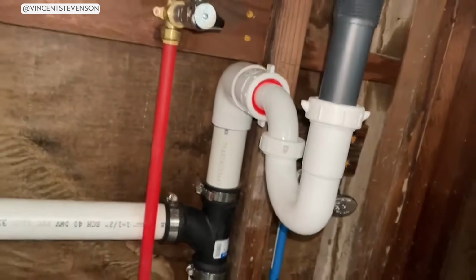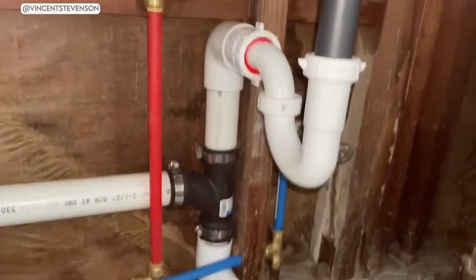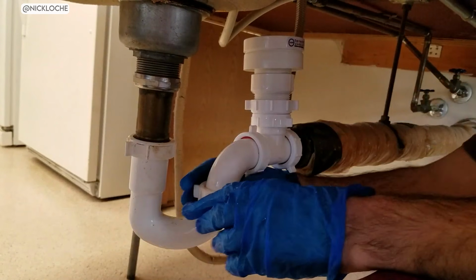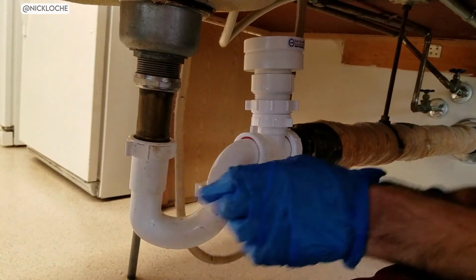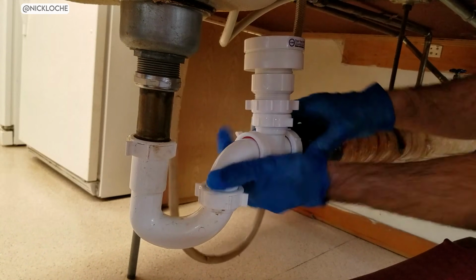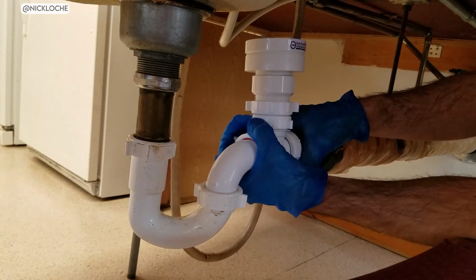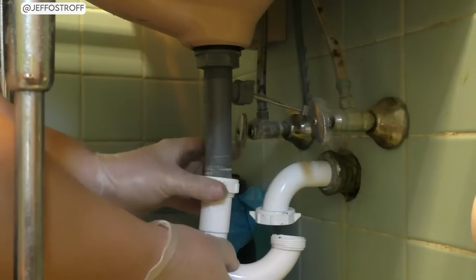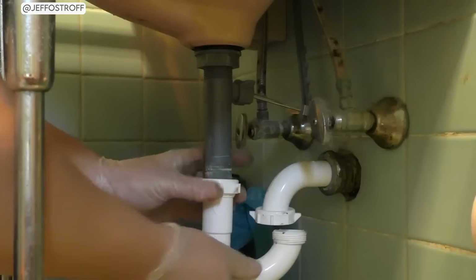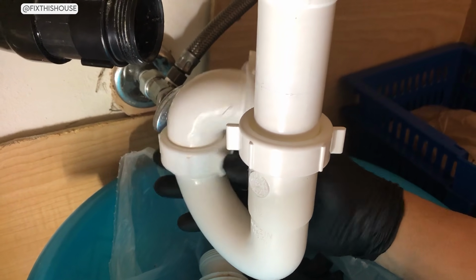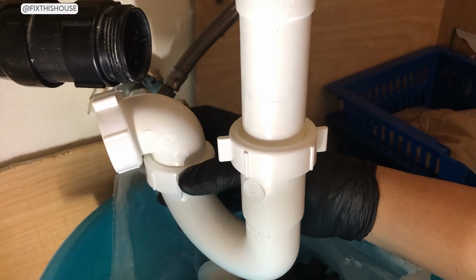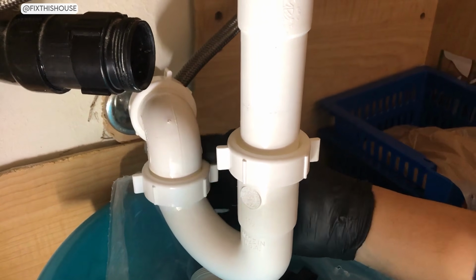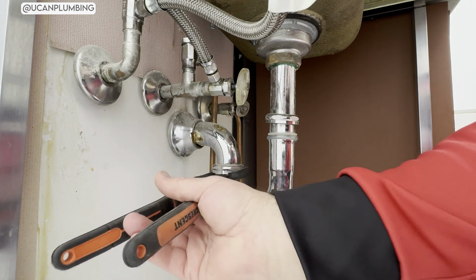In an S-trap, the pipe curves back down toward the floor, creating that full S shape. In a P-trap, the pipe exits horizontally, going straight back into the wall. When you look at a P-trap from the side, it actually looks like the letter P turned on its side. That horizontal exit is everything because it connects to a drain line inside the wall that is properly vented.